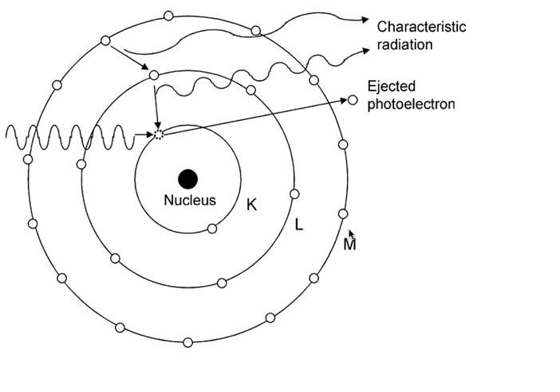I'll try to look for a typical x-ray spectrum and we can discuss that further. But for now, just focus that 99% of your x-ray production is going to go to heat, 1% goes to x-ray interaction. From that 1%, 85% goes to Bremsstrahlung and the remaining percentage goes to characteristic x-ray generation.